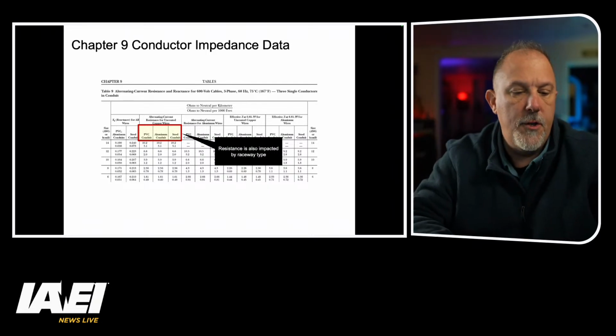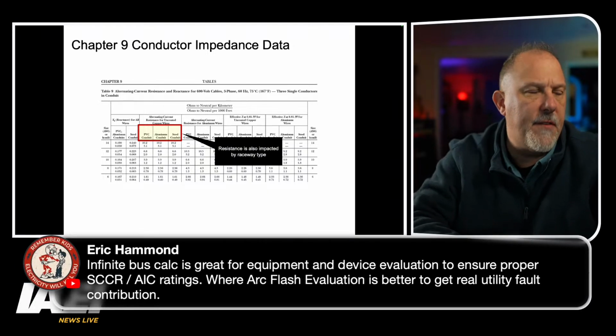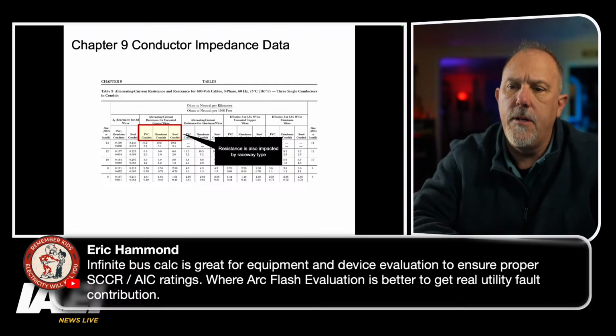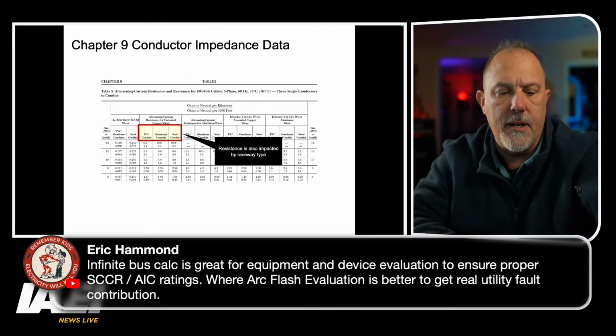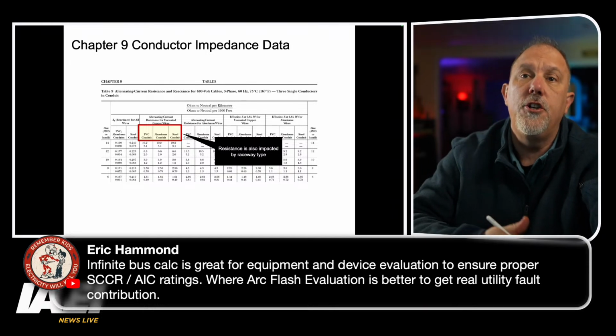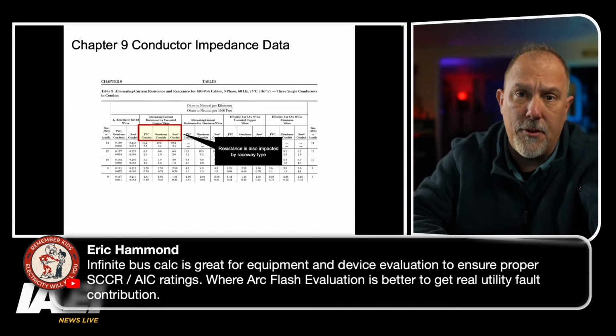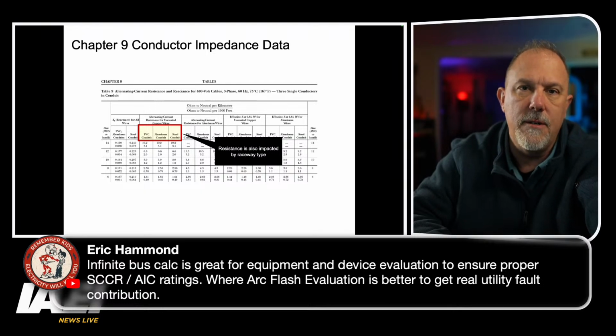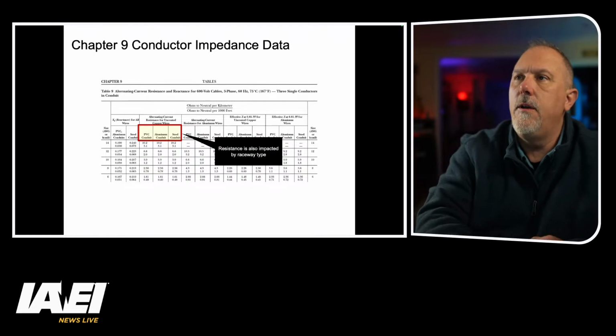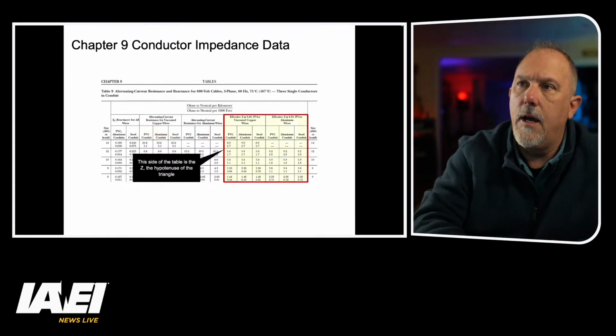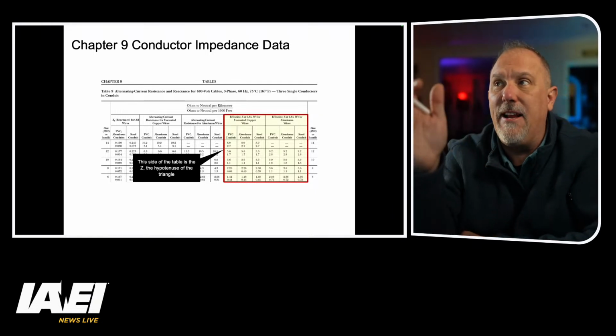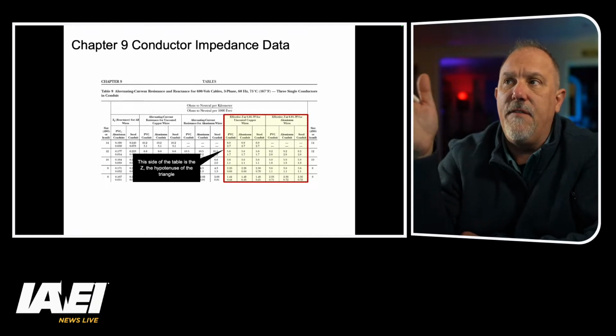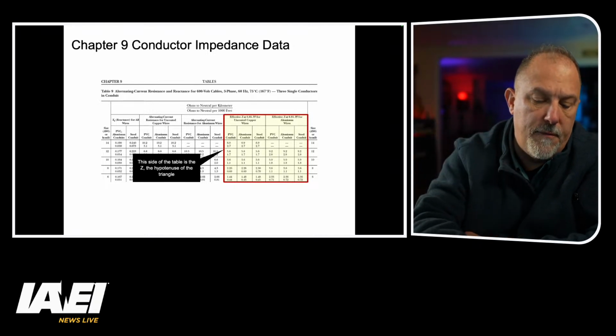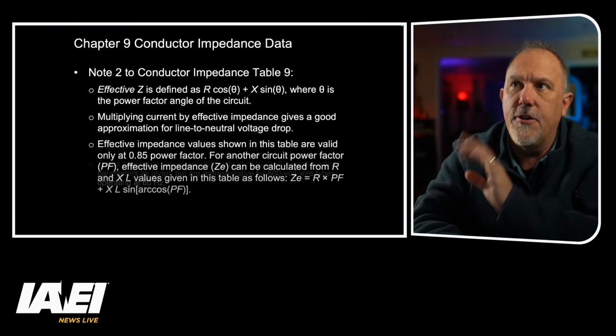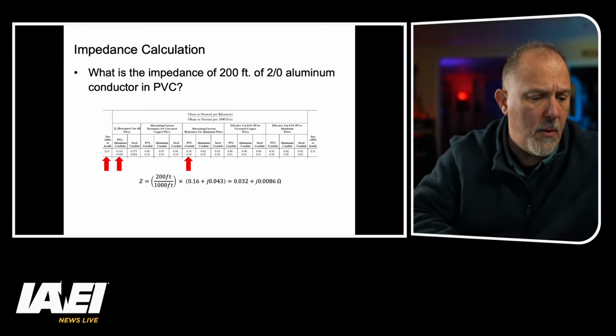Yes, Eric, the infinite bus is a very good method to calculate the maximum available fault current, because if your short circuit current ratings and your interrupting ratings exceed that value which you calculated, which will never be seen in the system because you've taken some assumptions, then you're good to go, right? So a conductor will have, and that over there is your effective Z at a 0.85 power factor. And I believe they would typically be able to use that for your voltage drop calculations. And there are some notes to follow up on.